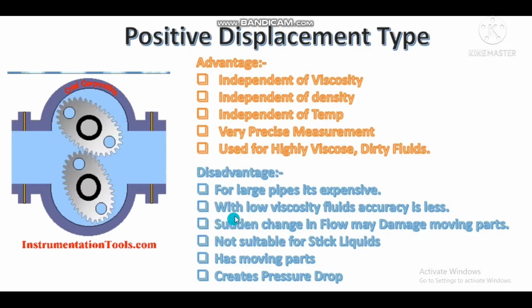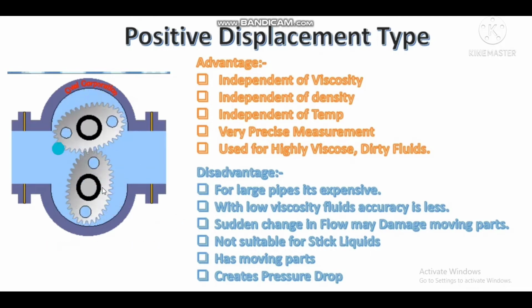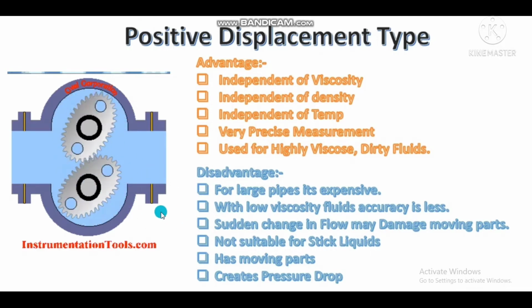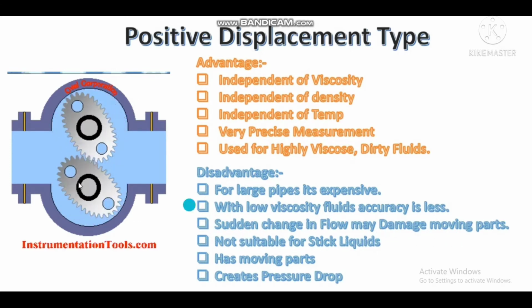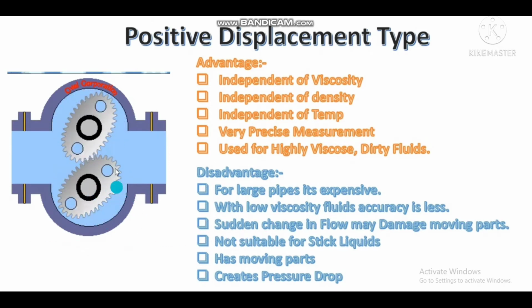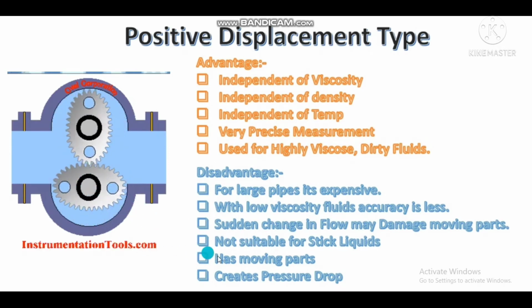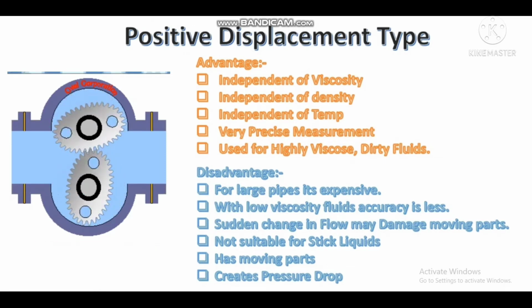Then the second one is that with low viscosity fluids, accuracy is very low. So it only applies to high viscosity fluids. The third one is that a sudden change in the flow may damage moving parts. There is a moving part here, and it can have wear and tear due to a sudden change in the flow, so we have to take precautions. And then it is not suitable for sticky liquids, like Fevicol or anything like this, adhesive liquids.